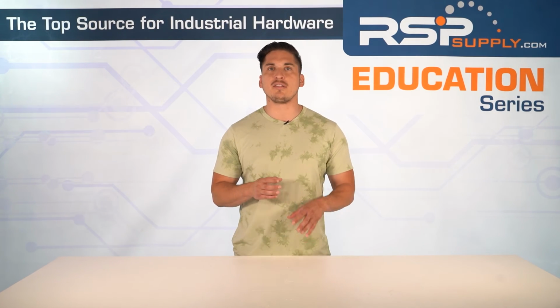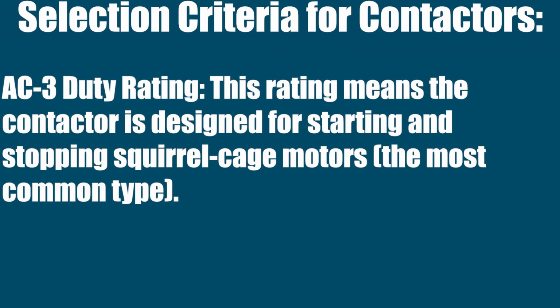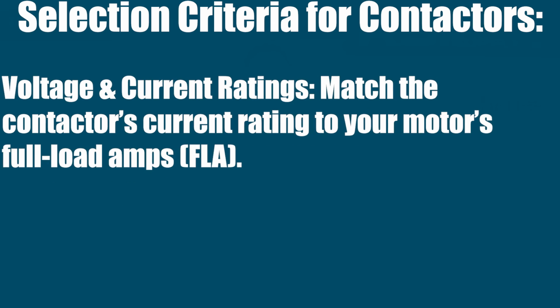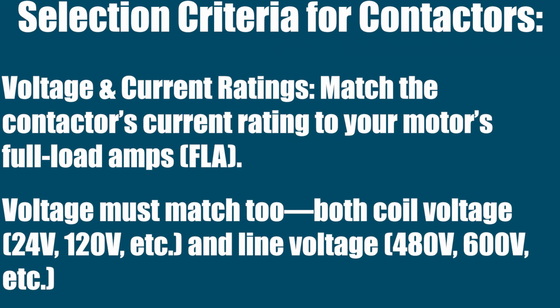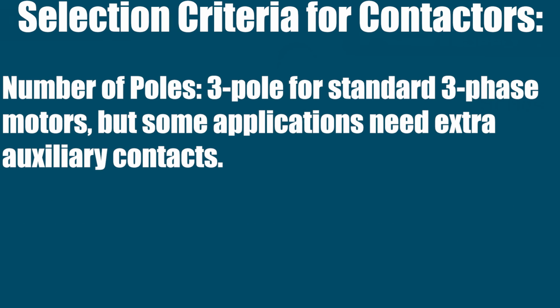Picking the right contactor is very important. Here's what to check for. AC-3 duty rating. This rating means that the contactor is designed for starting and stopping squirrel cage motors, the most common type. Voltage and current ratings. You need to match the contactor's current rating to your motor's full load amps, or FLA. Voltage needs to match too. Both coil voltage, typically 24 volt DC and 120 volt, as well as line voltage, typically 480 or 600 volt. Number of poles. 3 pole for standard 3-phase motors, but some applications need extra auxiliary contacts.